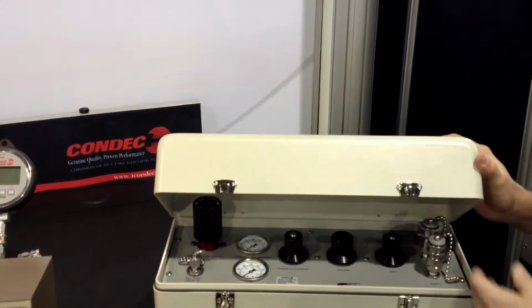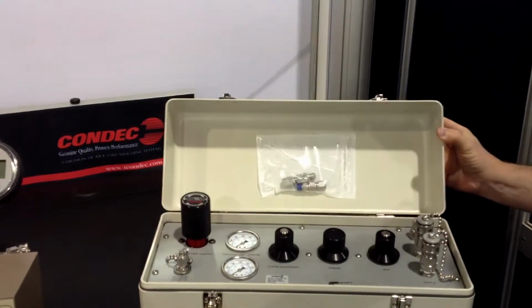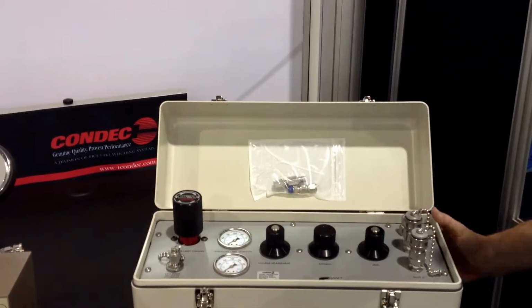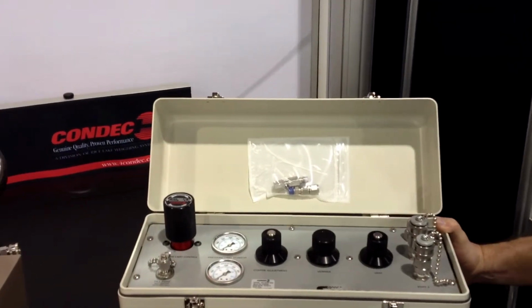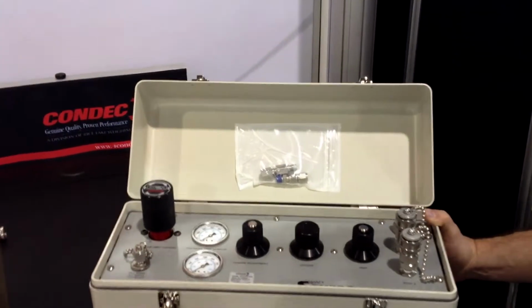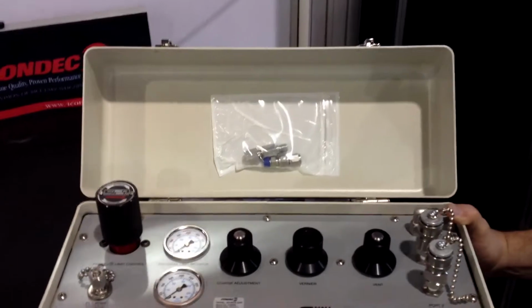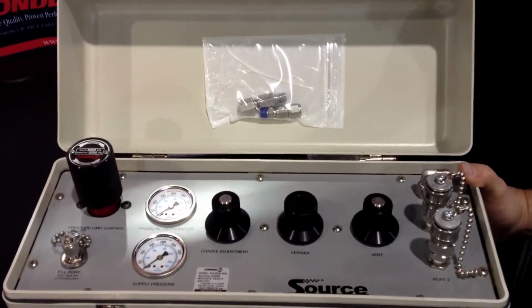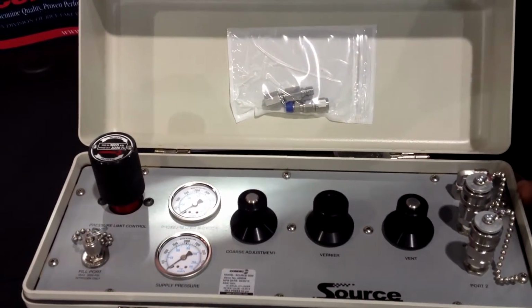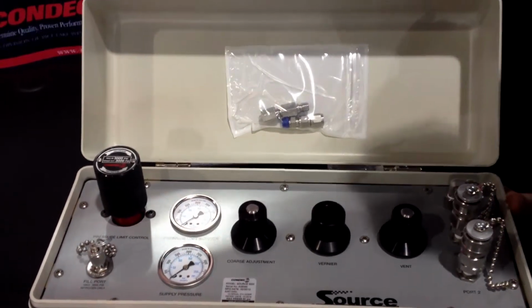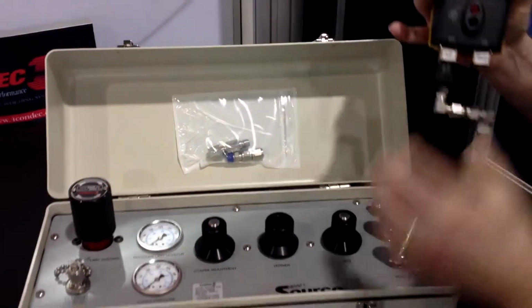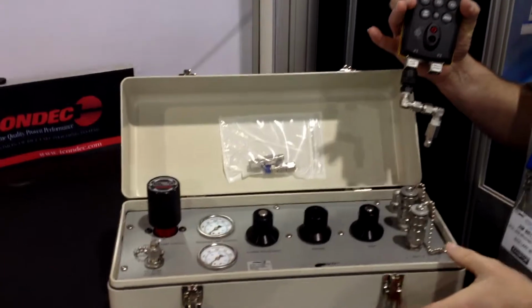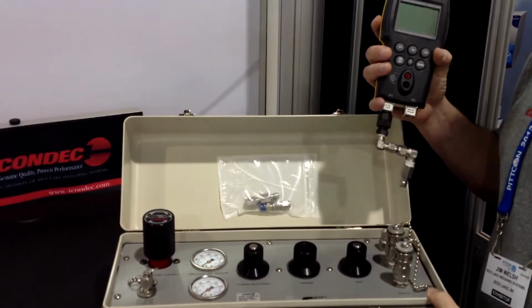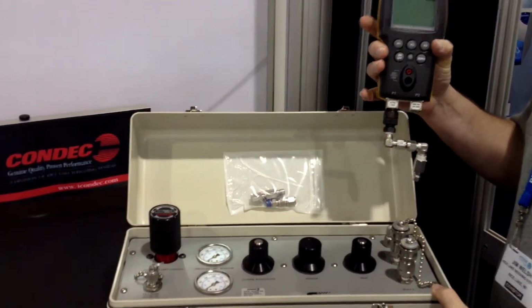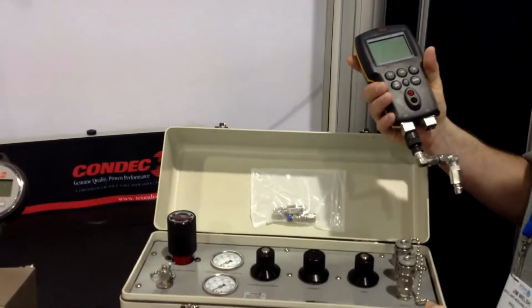Today we'll be speaking about the Source 3000. It's a unit you can basically take on site to use as a source of pressure for doing calibrations. What's nice about it is you can use anybody's handheld device as the calibration device. This is an all-mechanical device, so the source is not NIST traceable, but your handheld device would be.